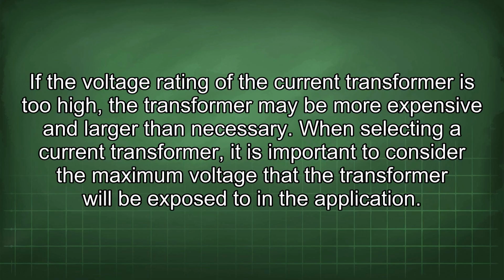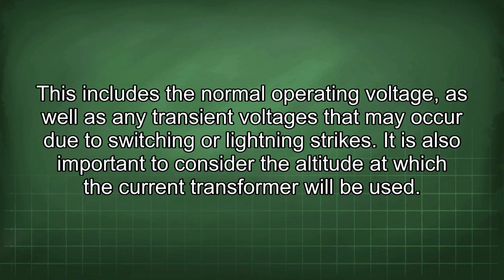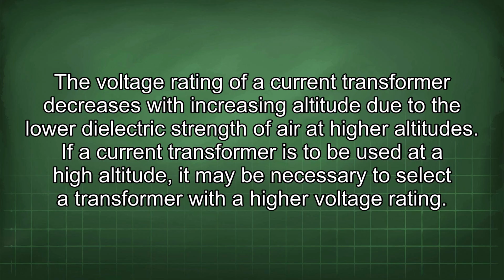necessary. When selecting a current transformer, it is important to consider the maximum voltage that the transformer will be exposed to in the application. This includes the normal operating voltage, as well as any transient voltages that may occur due to switching or lightning strikes. It is also important to consider the altitude at which the current transformer will be used. The voltage rating of a current transformer decreases with increasing altitude due to the lower dielectric strength of air at higher altitudes. If a current transformer is to be used at a high altitude, it may be necessary to select a transformer with a high voltage rating.